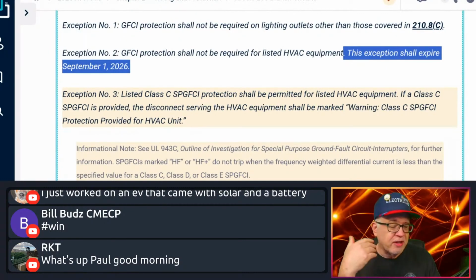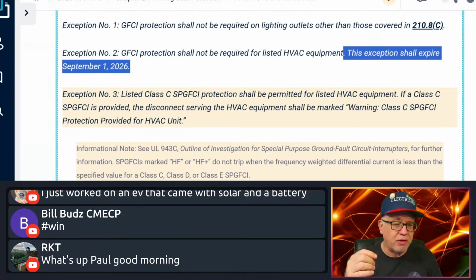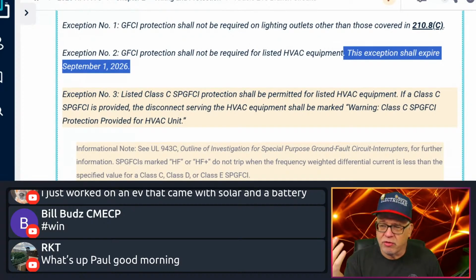So there's still a sunset date in there, and again, for all those out there who need to understand, this doesn't matter whether it's hardwired or cord and plug, although I don't know any outdoor HVAC equipment like this that would be cord and plug outdoors. So it's typically going to be hardwired from an outlet, all right? You can get away with not having the GFCI protection until September 1st. But if you choose, then you can go with a Class C SPGFCI, okay? But you have to mark it as such to be able to achieve that, okay?